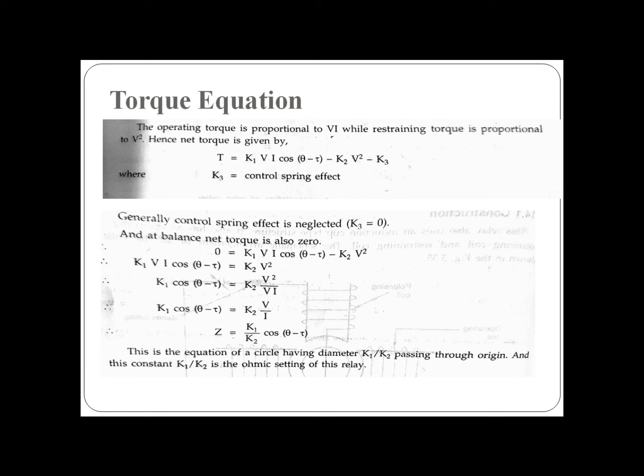So basically, what you have in Mho relay is that the operating torque is the product of voltage and current, and the restraining torque is proportional to the square of the voltage. One torque produces K₂V², and the other torque produces VI cos(θ - τ).